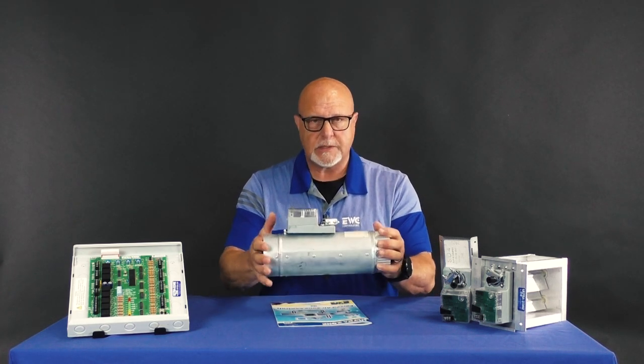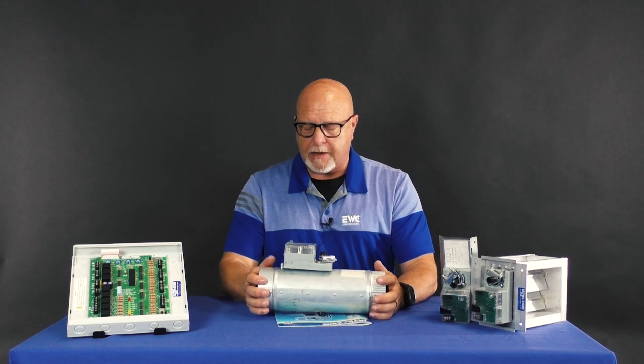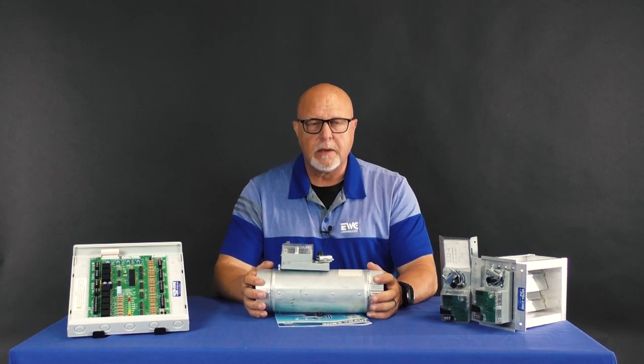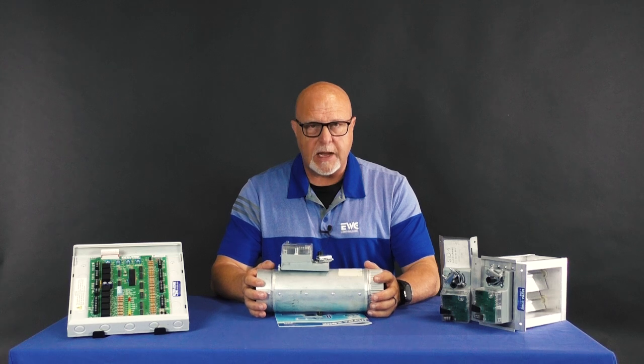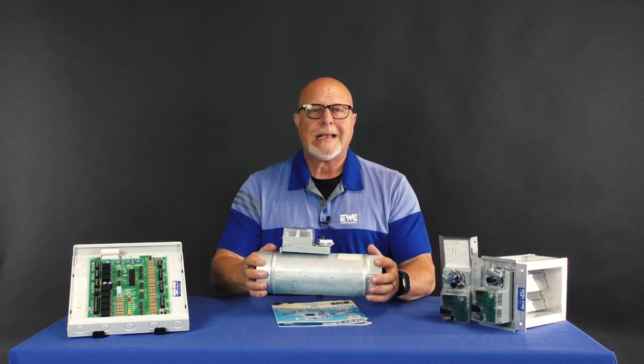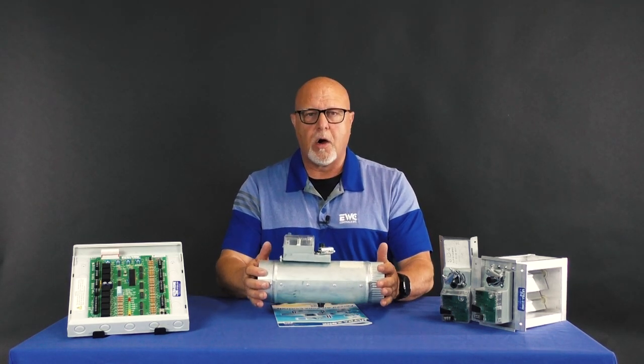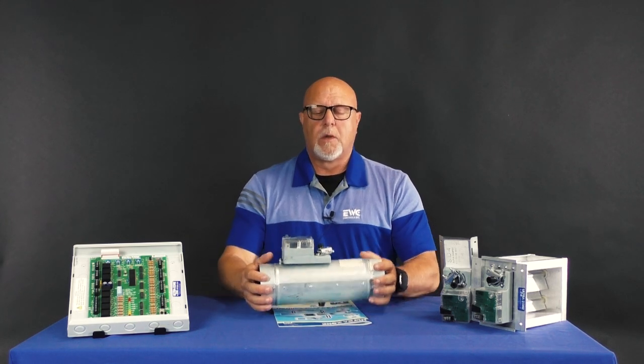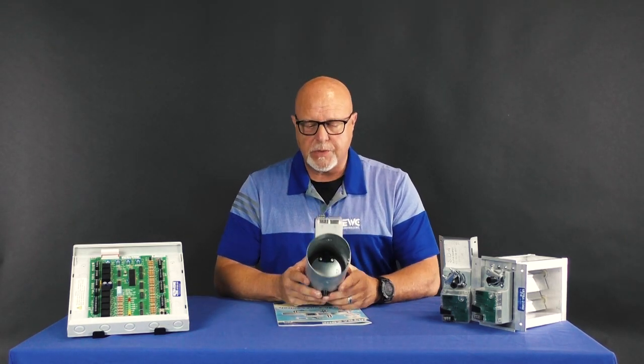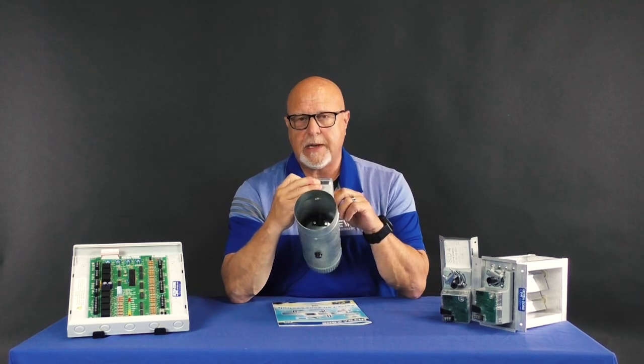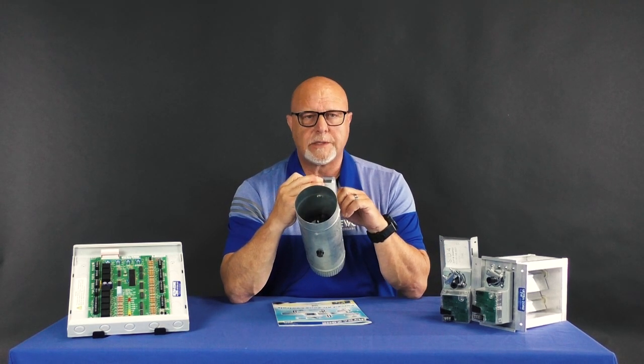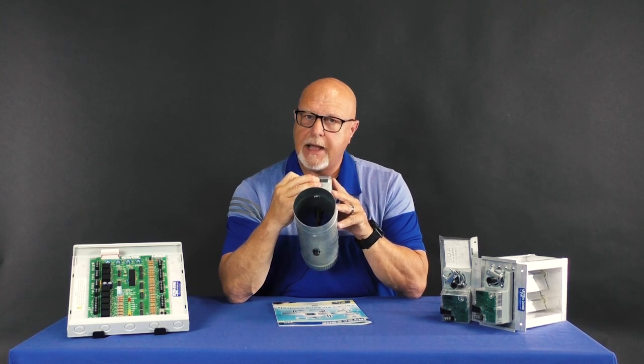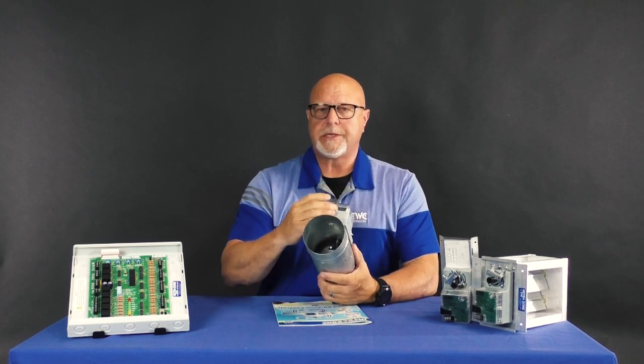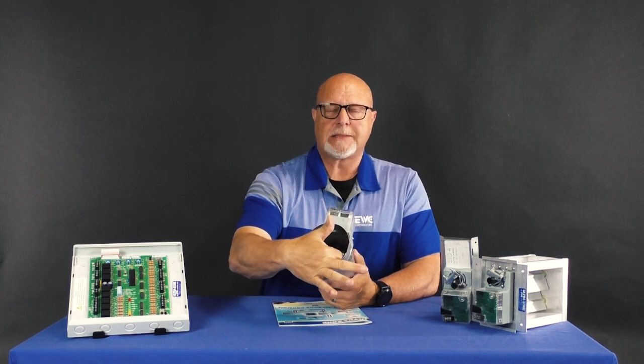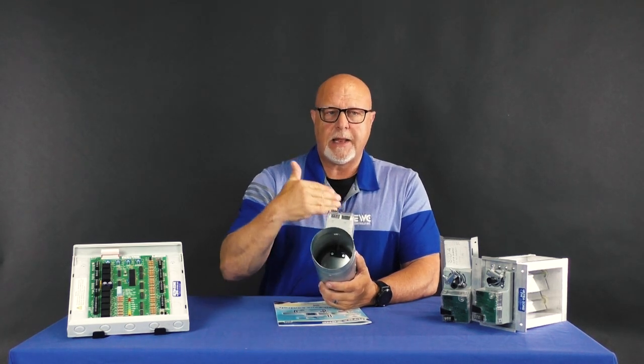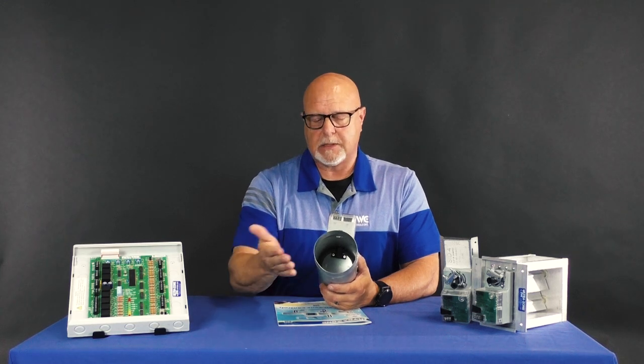It's very robust and very strong. But I will say that sometimes after it's been on a job site, these dampers are not always truly round. We have tried to compensate for that by putting a pour-on cellular foam gasket inside of here, where our competition will glue a gasket, a foam gasket, and they will actually close the blade to the gasket.